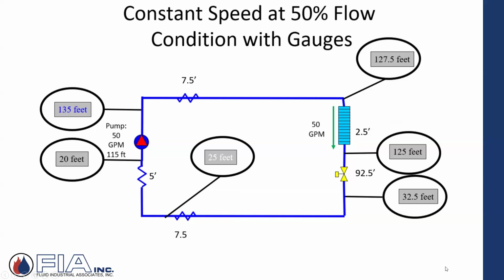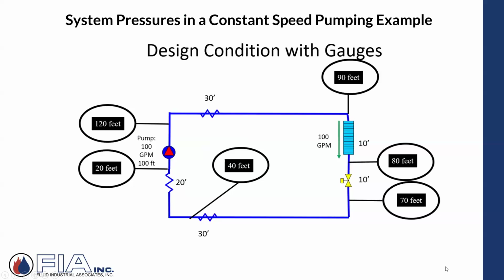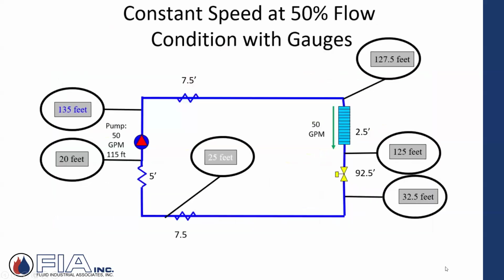But I've got a quick question for you here. When I look at the design conditions and I see the pressure drop that's been calculated, and you did the calculation a while back, and this is what you come up with on your plan. And all of a sudden you're saying, hey, when real world conditions exist and I have part load conditions, in this case say 50% of flow, 50 gallons a minute, I can assign different pressure drops because those pressure drops are real. They're going to change. Why? How do I know those numbers are right? Where do they come from?